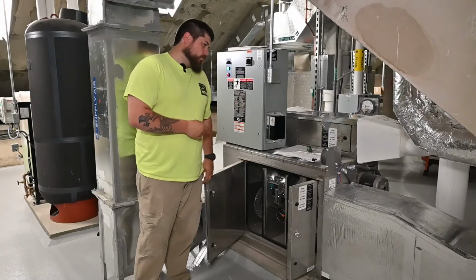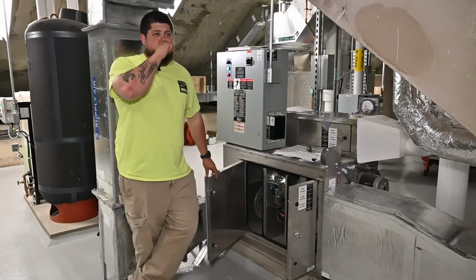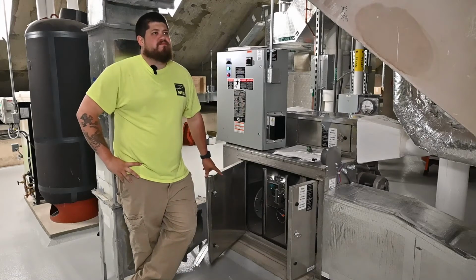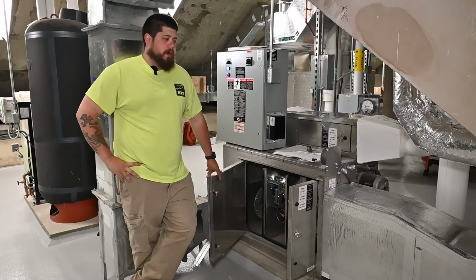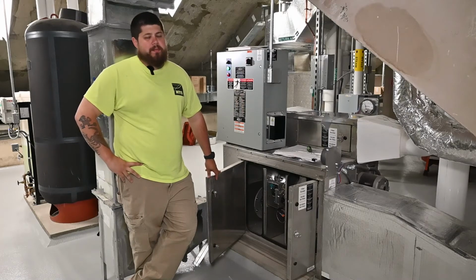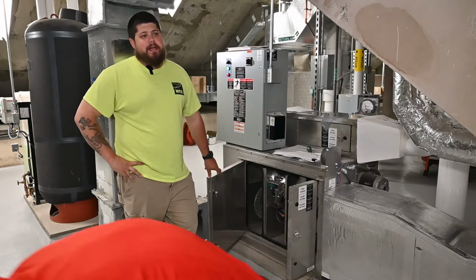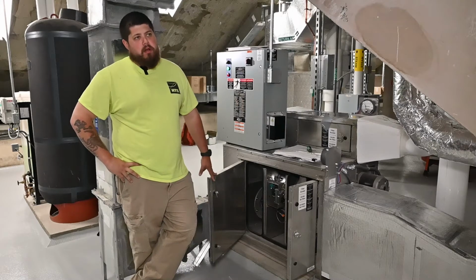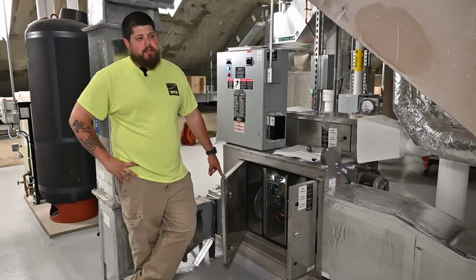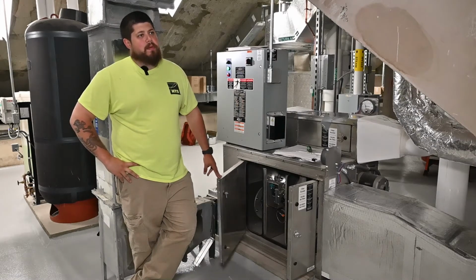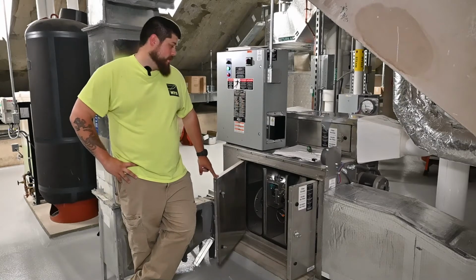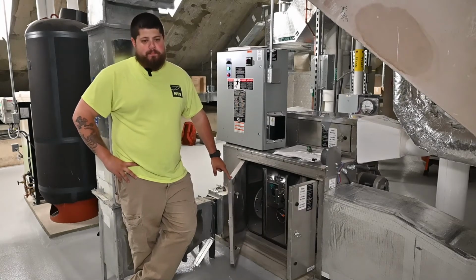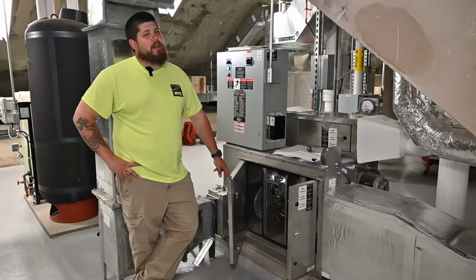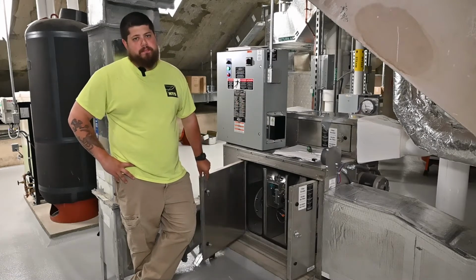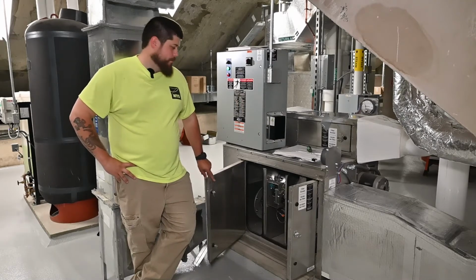You've got a desiccant wheel inside of here. This one's a little different than the one up there. The only reason I say that is obviously location based. As far as maintenance goes, if you make sure of any filters that get changed, I strongly recommend it be this. Because if that gets dirty, there's not an easy way of cleaning it. And frankly, if it gets dirty enough, there isn't a way of cleaning it, and it'll have to get replaced.